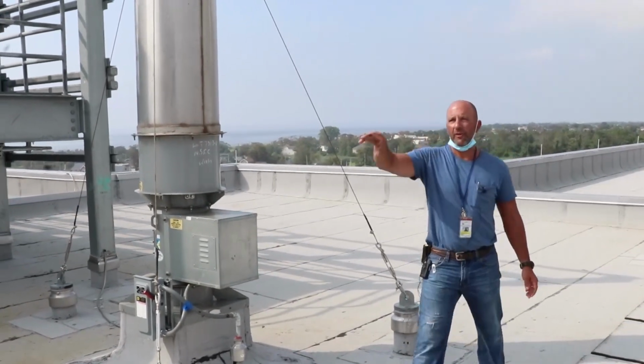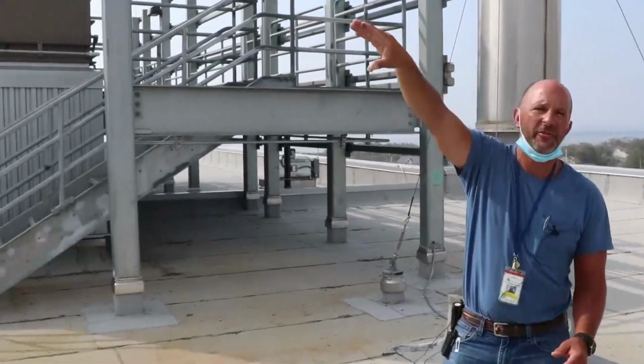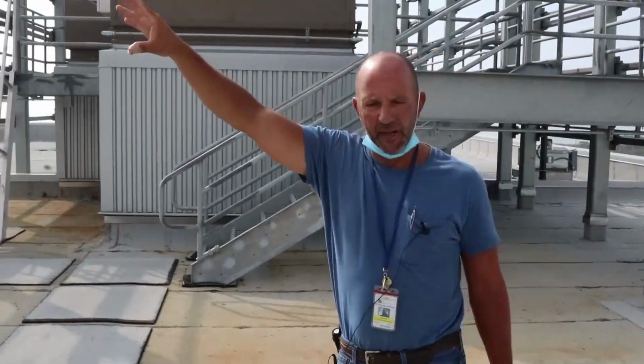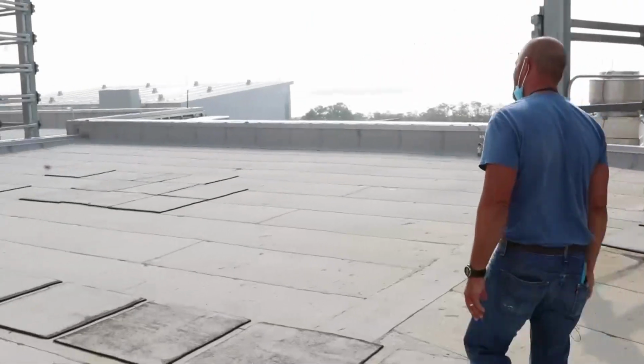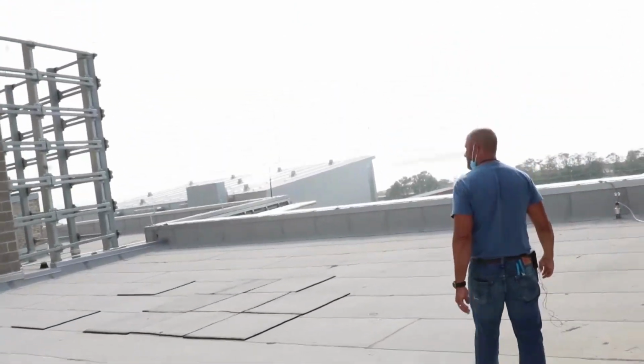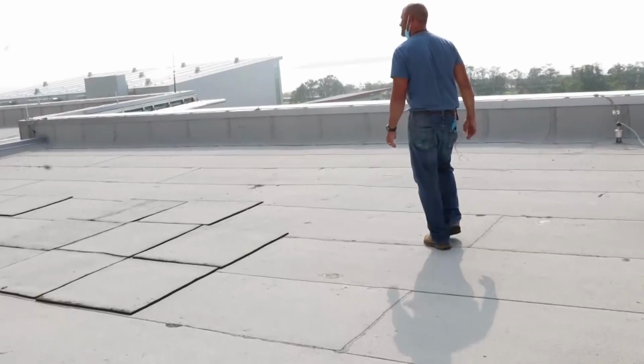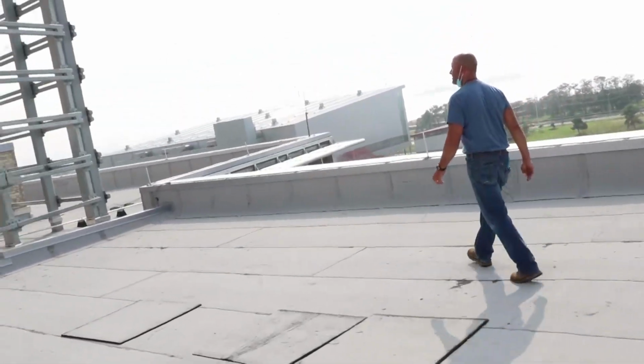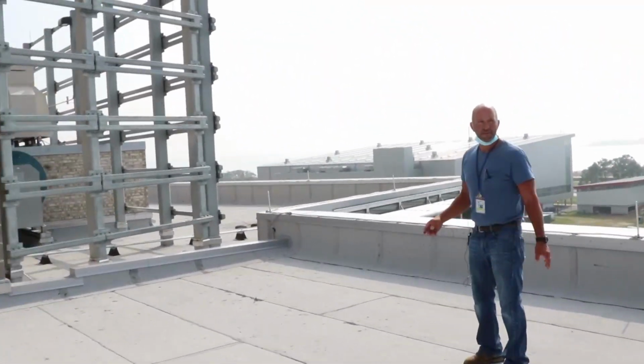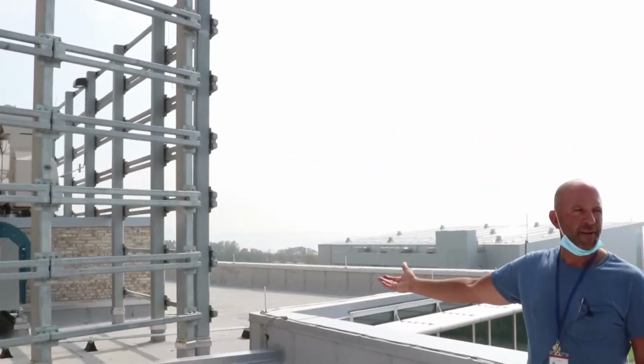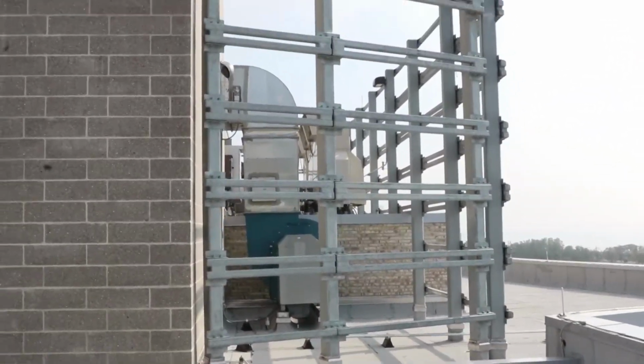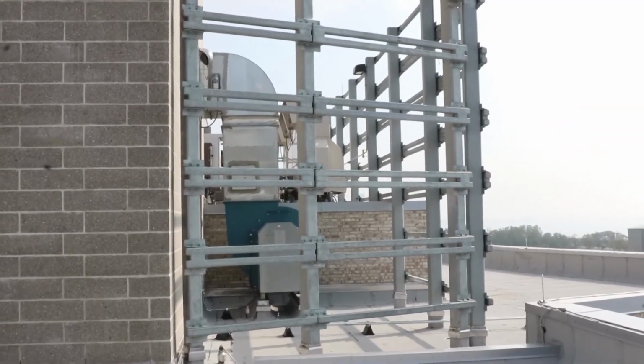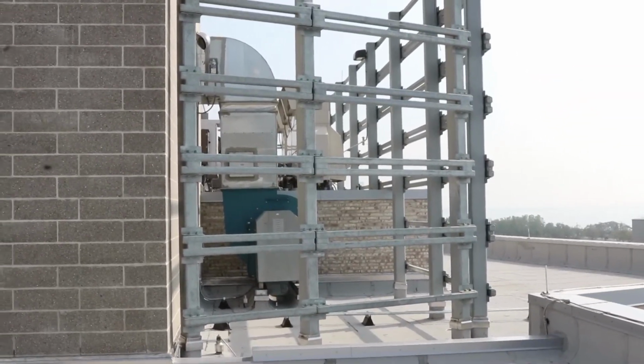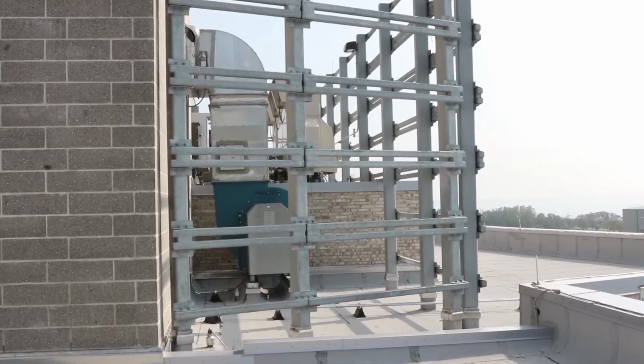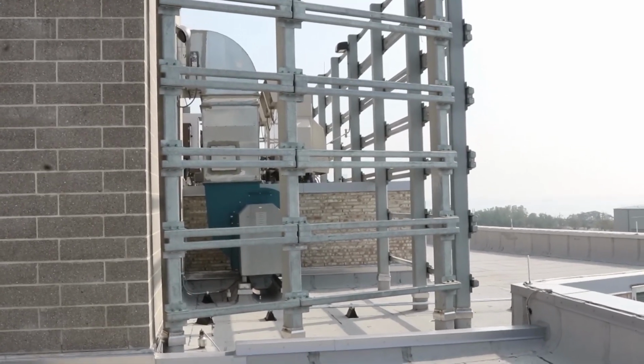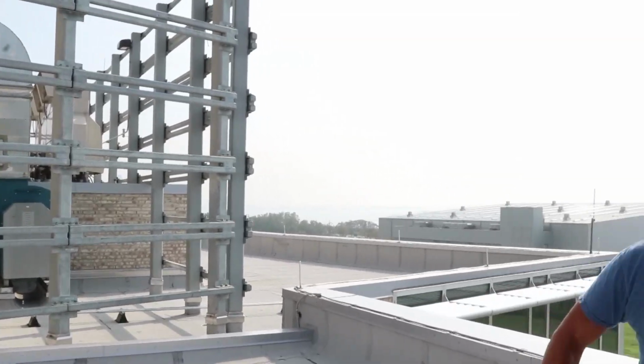Let's just take a walk around. So we saw that EPF fan that feeds the fresh air into the actual elevator machine room, right? Now you have this one over here. Much bigger horsepower, bigger fan, because it's also for elevator. Yeah, so basically it's pushing air into the top of the shaft on top of the elevators and forcing it downward. All right, it's just an open duct that goes into the shaft. It's not like it's ducted all the way down, but it pressurizes the shaft.